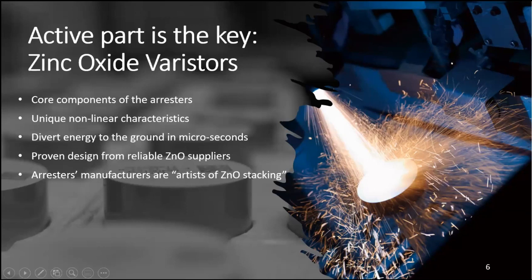The key component of the surge arrester is the zinc oxide varistor. As arrester manufacturers, we see ourselves as artists of ZnO stacking — playing with the number of blocks, the type of blocks, and the diameter of blocks. These components have a unique non-linear characteristic that diverts energy to ground in microseconds. Since the 1980s, zinc oxide varistors have been a proven technology for handling overvoltages.